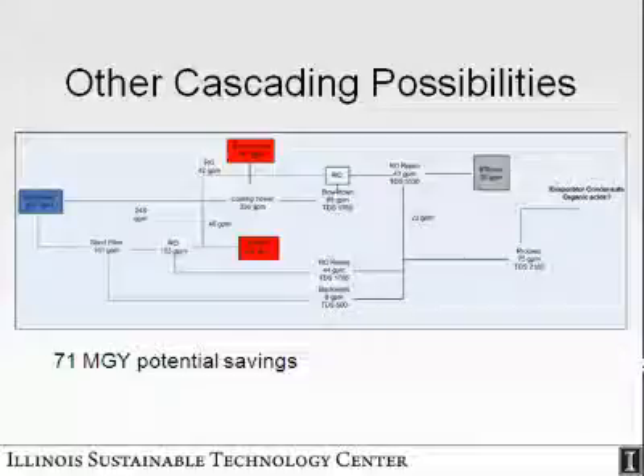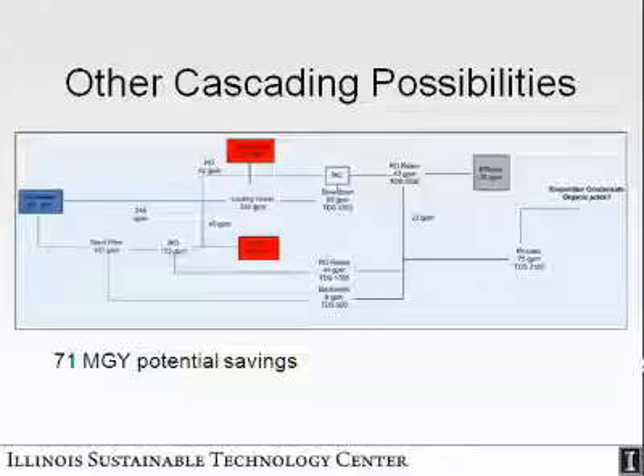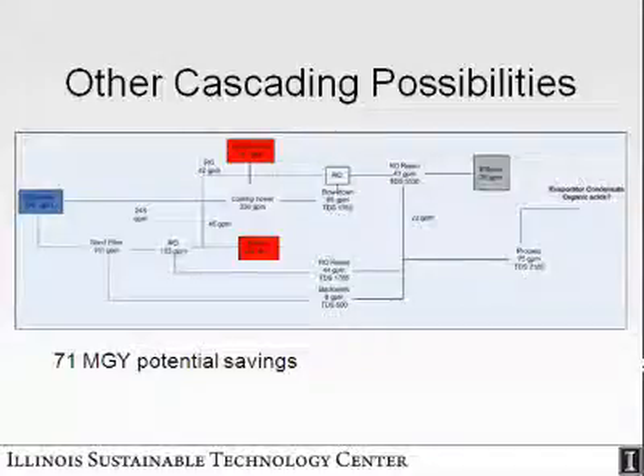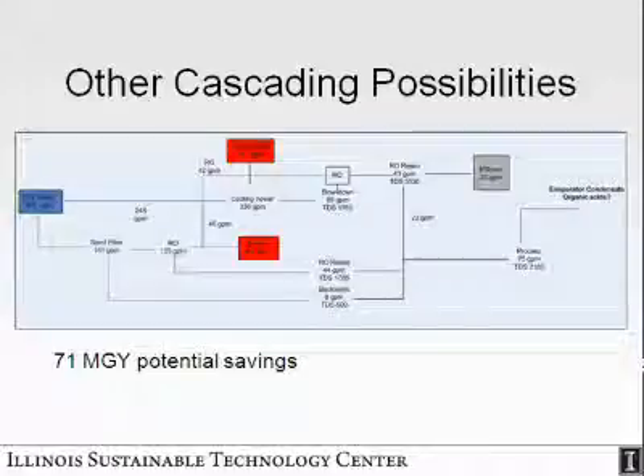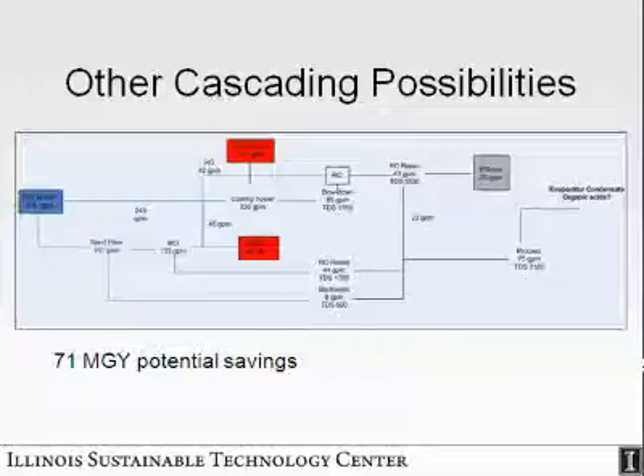So the real opportunity is, if you can clean up this particular stream that has these acids, and lower it using some other technology, you could probably use water at maybe 5,000 or 6,000 ppm total dissolved solids content, whereas right now most people tend to limit it to about 1,000 ppm maximum in their plant operations.